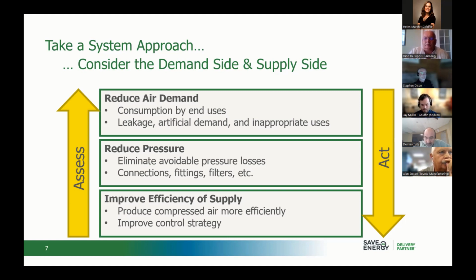Now, what's interesting about that one too is that sometimes that can have an impact in other parts of the plant or the operation as well, because it may be that somebody opens that valve to clean the floor in the machine shop, but that creates a pressure transient in the system, which causes problems elsewhere. In order to overcome that, we jack the pressure up even higher in the system, whereas maybe we could deal with the inappropriate use, or if the use is appropriate but still transient, deal with that with appropriate storage capacity, which moves us back into the other parts of the system.